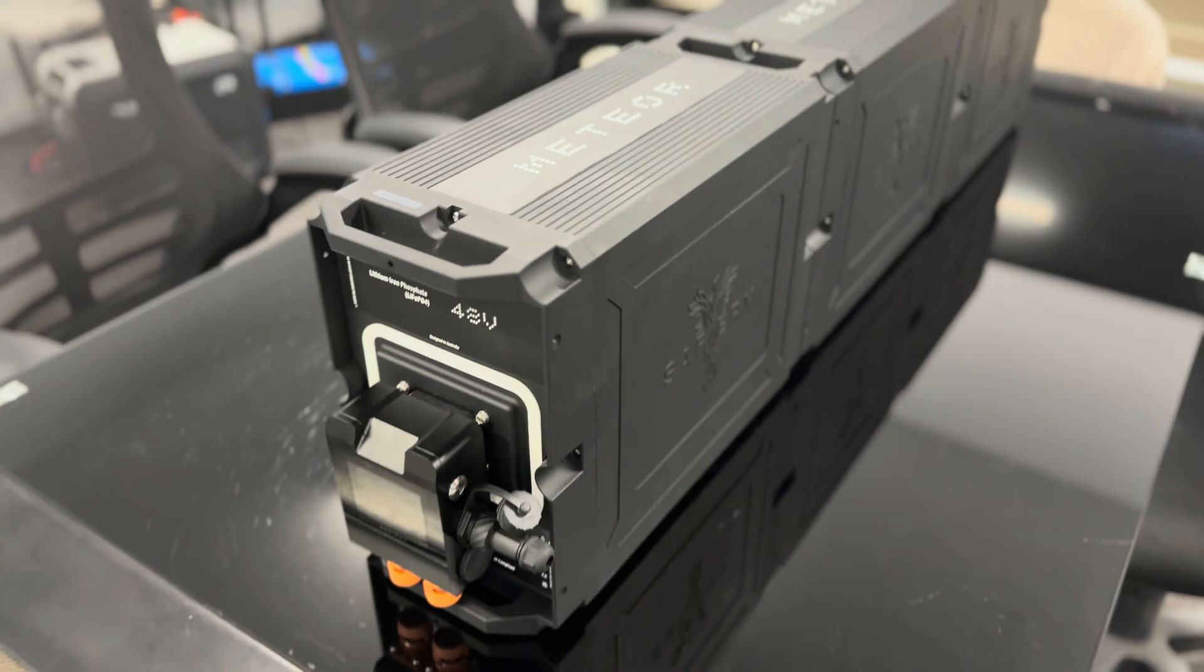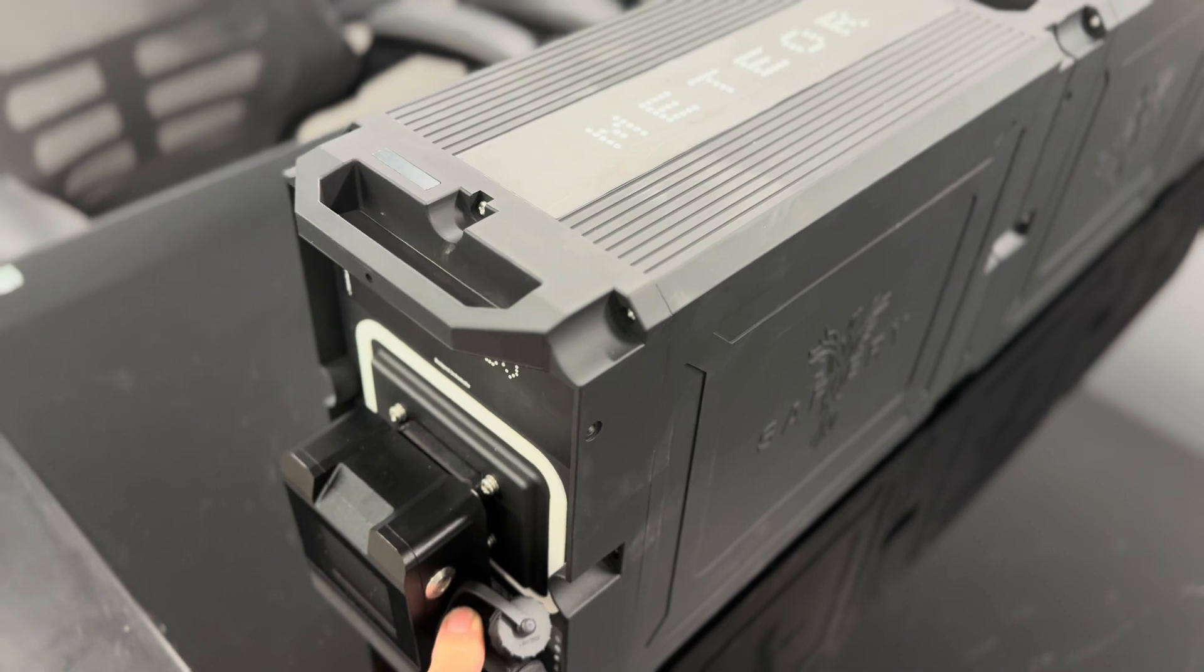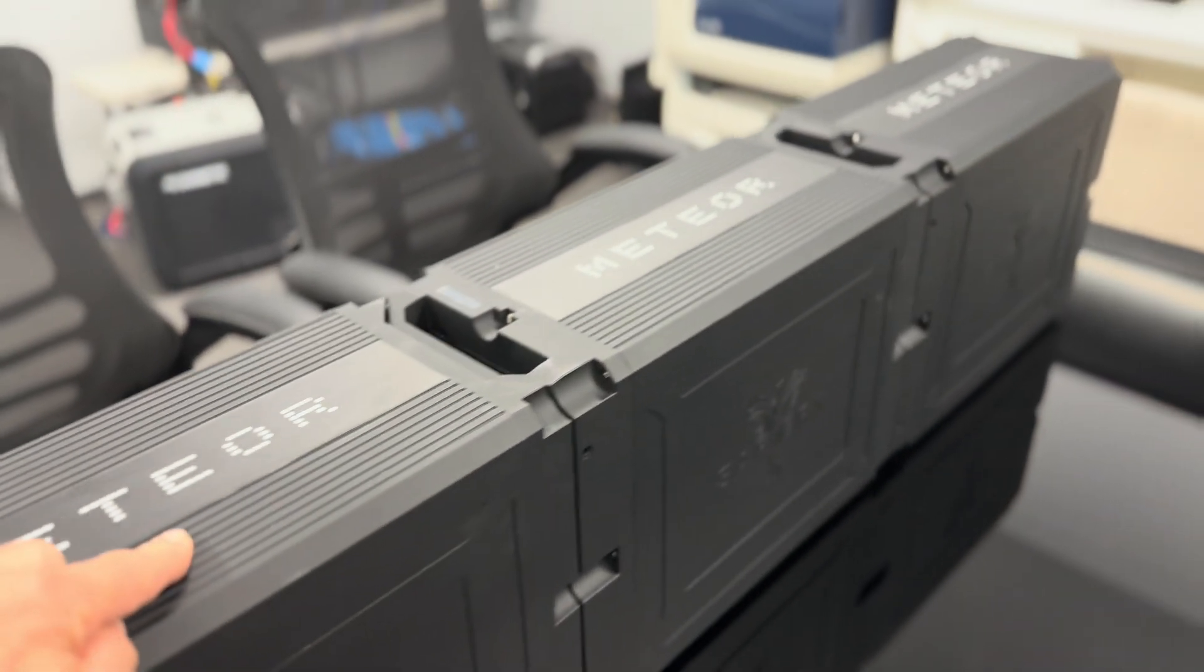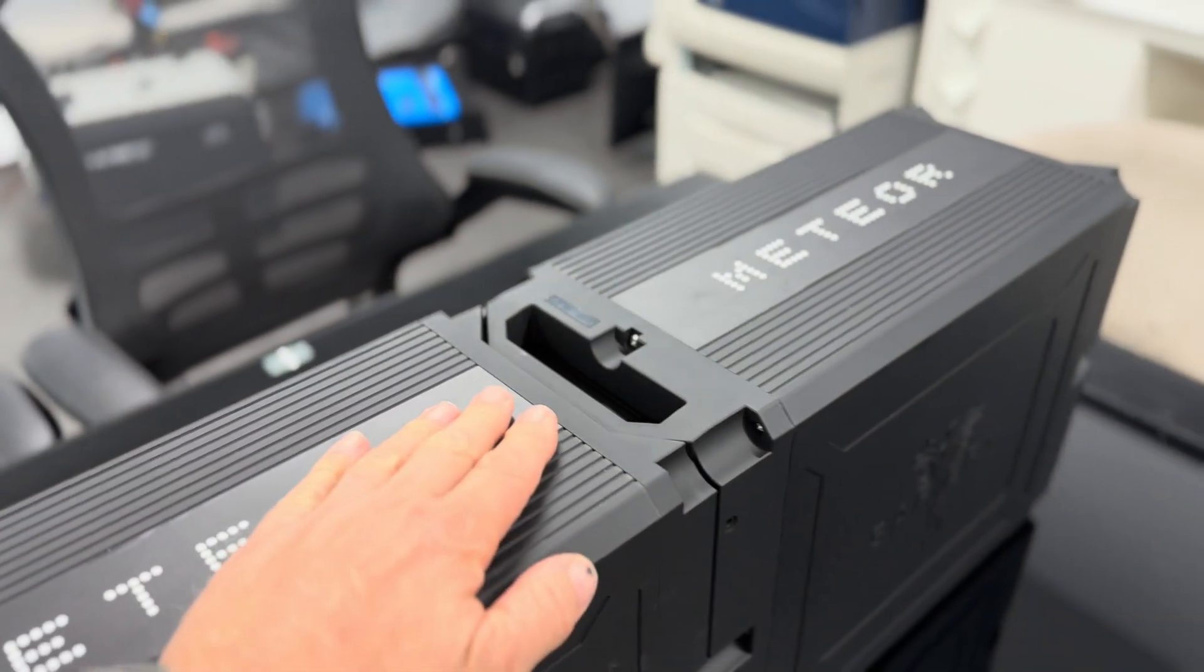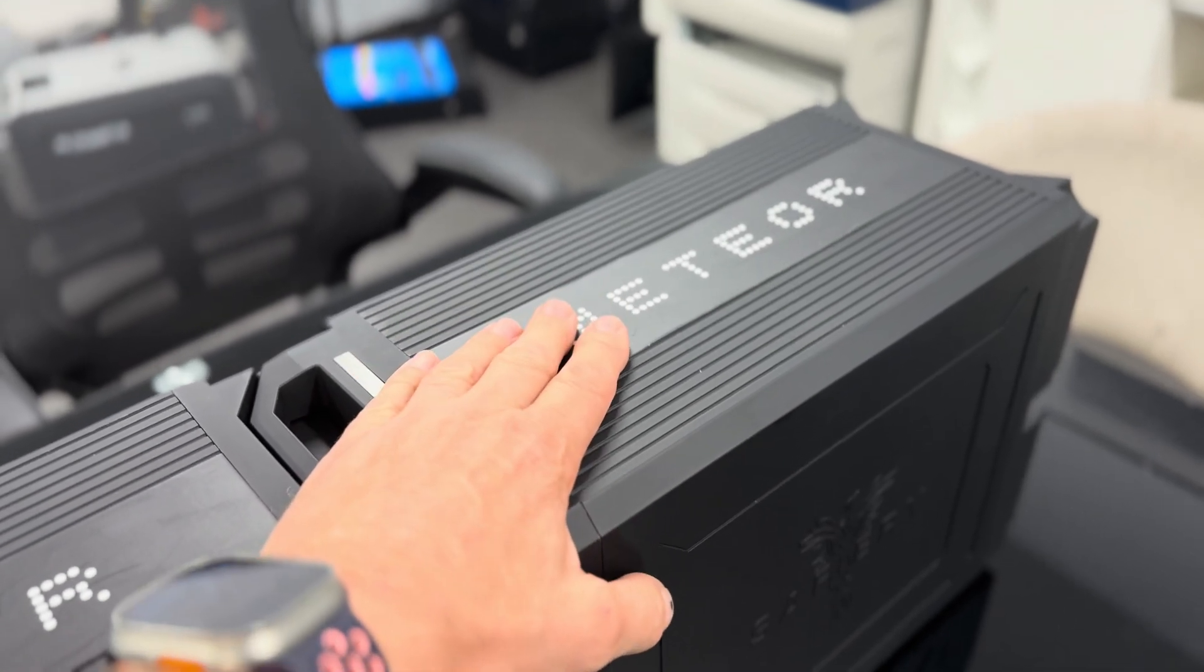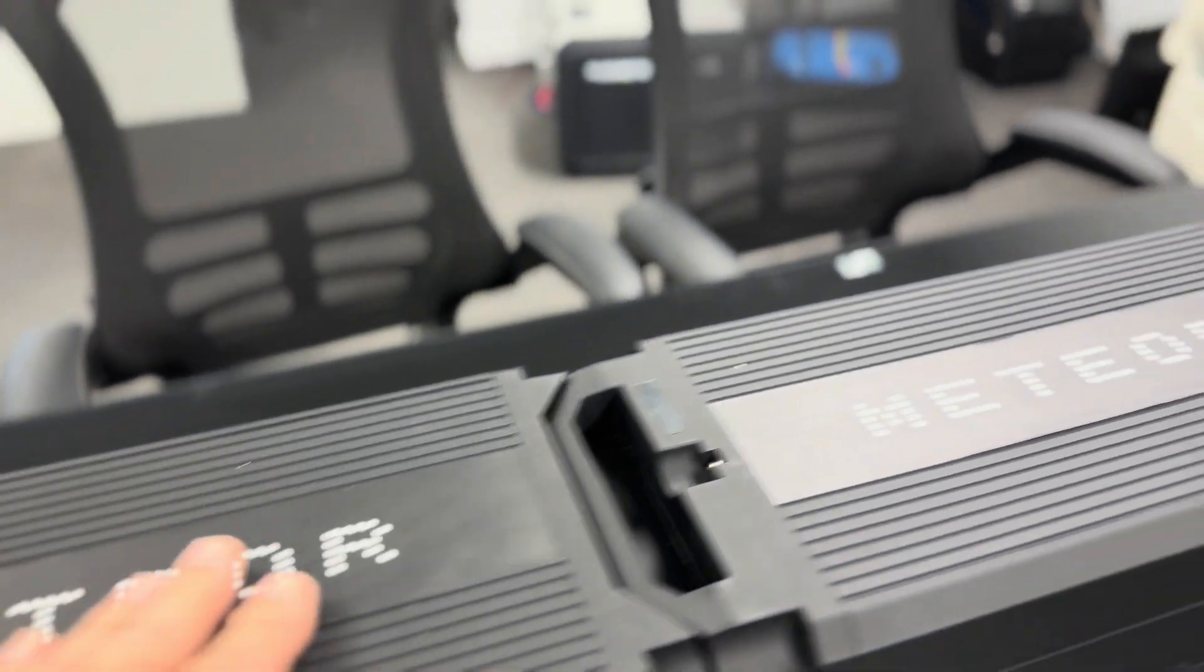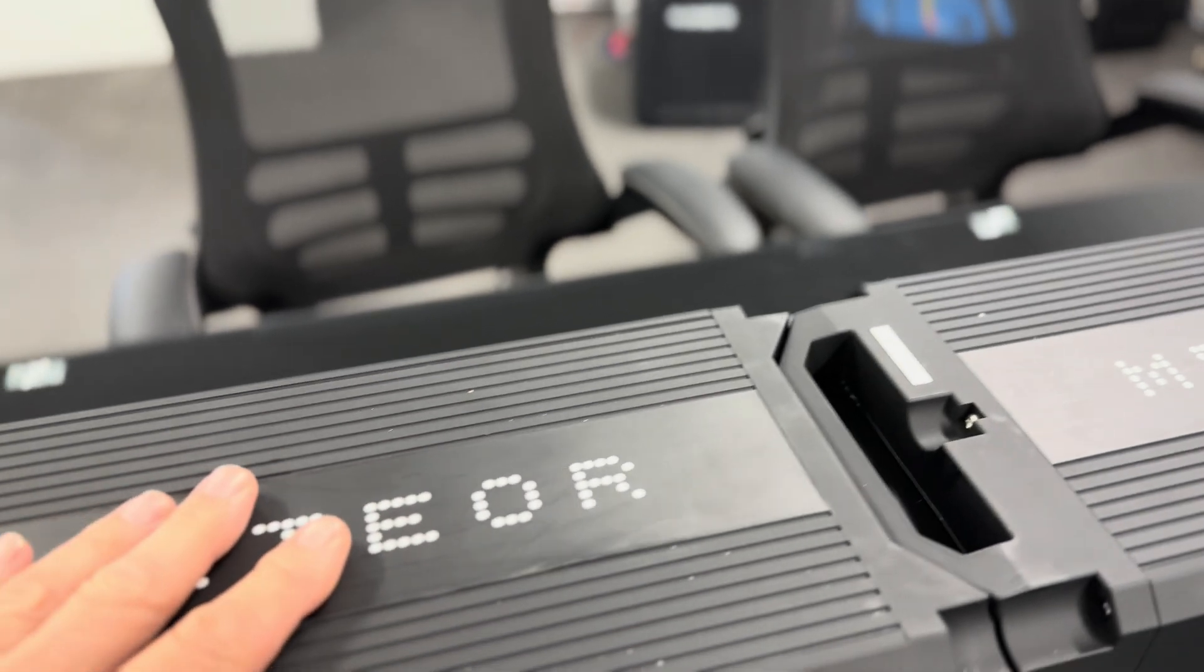Now from a safety point of view, if there's a corruption on the CAN here, whatever may happen on the external communication, these batteries are talking internally. I've got 485 Modbus running between them. If this battery reaches over temperature or any risk at all on it, it will turn all the batteries off. So we've got a bus running in here in parallel that will turn them all off.